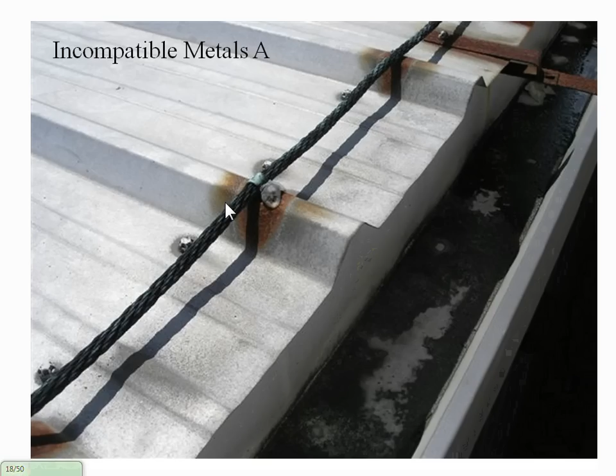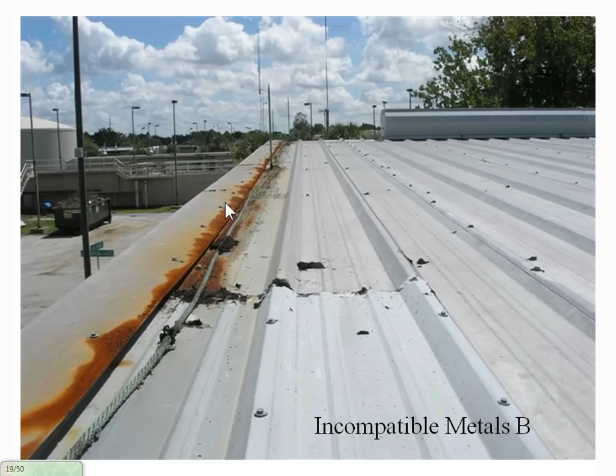This was even, you can see where the cable's placed and where it actually is oxidizing. Anywhere in between or near this cable. Basically, the moisture, the air, all affect how the cable interacts with the material that you're applying it to. So that's this space here with an aluminum air terminal on it. Well, with copper. This corrosive area here, it's actually starting to eat through the roof. So it's just one thing to keep in mind is what kind of material you're using and what you're mounting to on your roof.